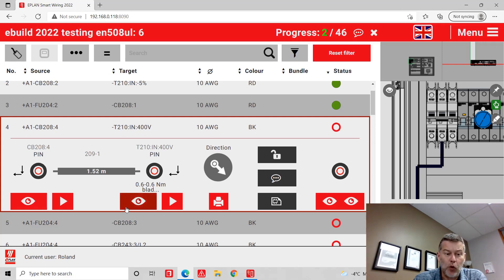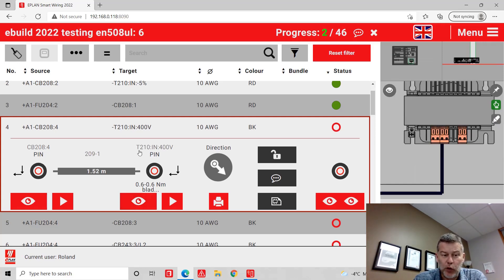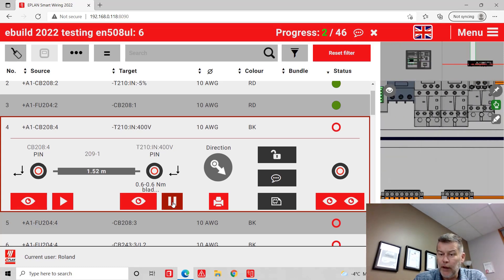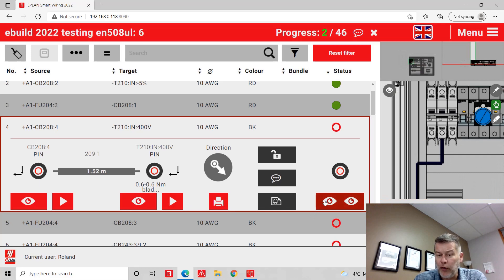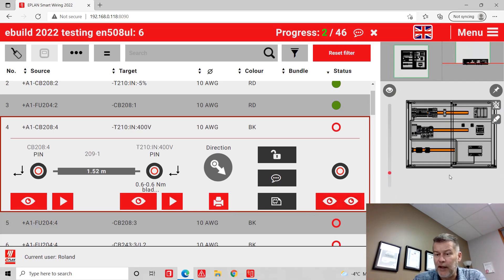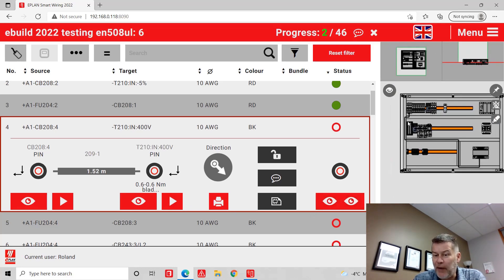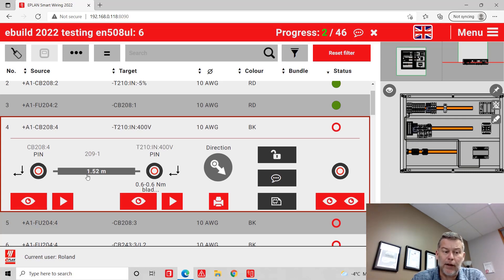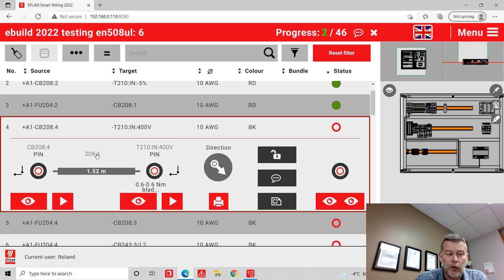The idea is: where is CB208 pin 4? Where is transformer T210? How do I get from one to another? If I want to display the whole thing, I can see the full path — it will zoom in and show you exactly the path. The length I have to cut is exactly one meter, 52 centimeters. The wire number I'm going to assign is 209. Once I've finished one side, I simply click here and it tells me I've done this side.